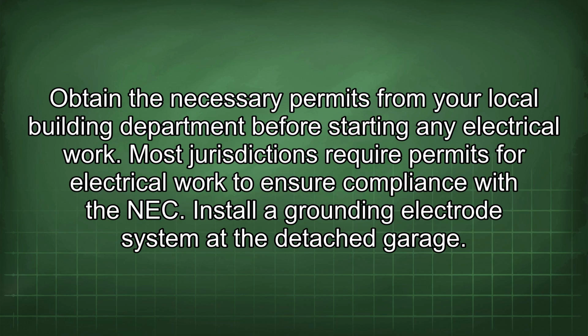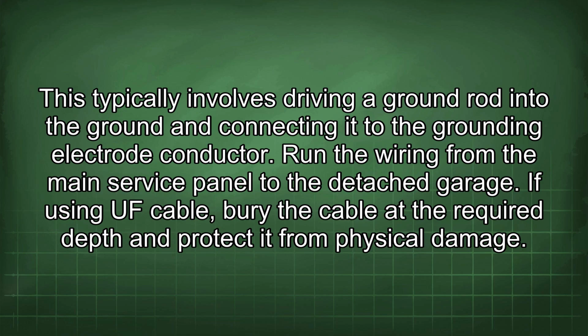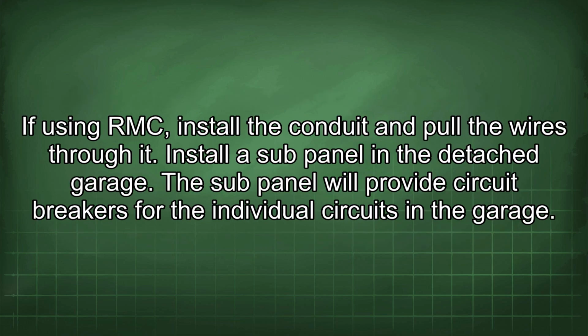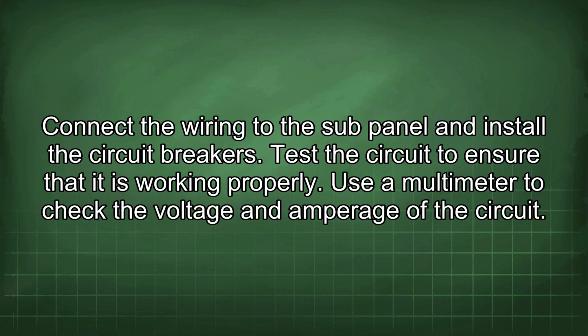Install a grounding electrode system at the detached garage. This typically involves driving a ground rod into the ground and connecting it to the grounding electrode conductor. Run the wiring from the main service panel to the detached garage. If using a UF cable, bury the cable at the required depth and protect it from physical damage. If using RMC, install the conduit and pull the wires through it. Install a sub-panel in the detached garage. The sub-panel will provide circuit breakers for the individual circuits in the garage. Connect the wiring to the sub-panel and install the circuit breakers.